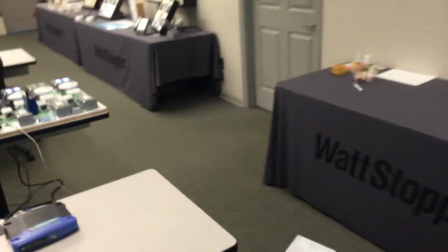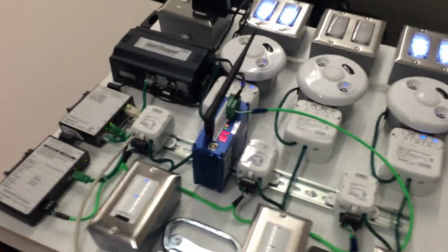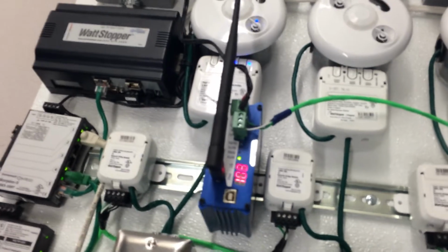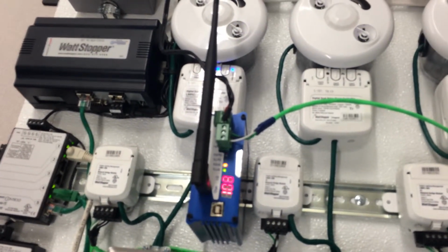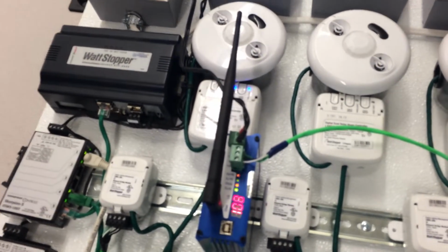Down here at the bottom is where he's got control of the DLM networks. 2 of these rooms are in the building that we're hardwired to, and that third room over there is actually connected to the remote building. So let's go over there and take a look at that. And Elliot, what I'd like for you to do is start to use the trunking capability, the wireless trunking, the second technology that we're demonstrating here. This RF transmitter just takes the BACnet messaging off the MSTP wire and puts it on a virtual wire, or an RF transmission, over to a remote building.